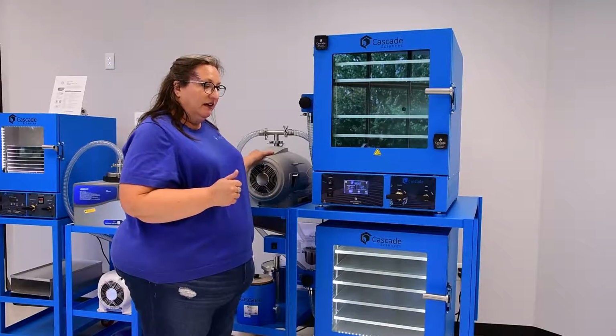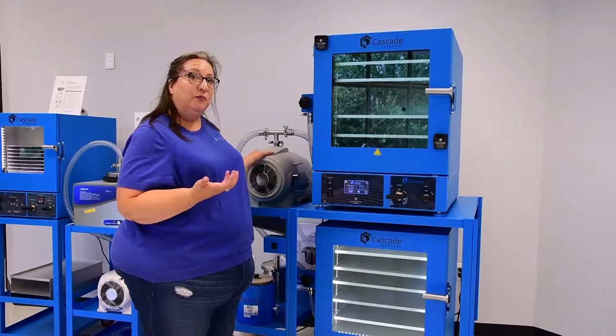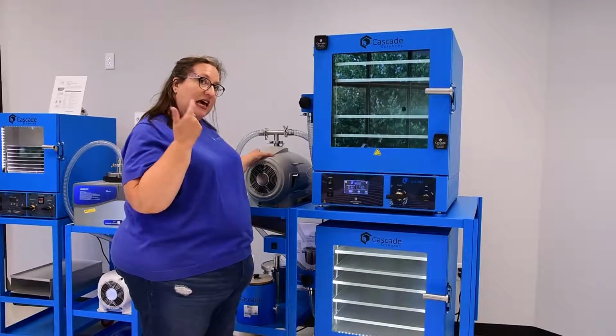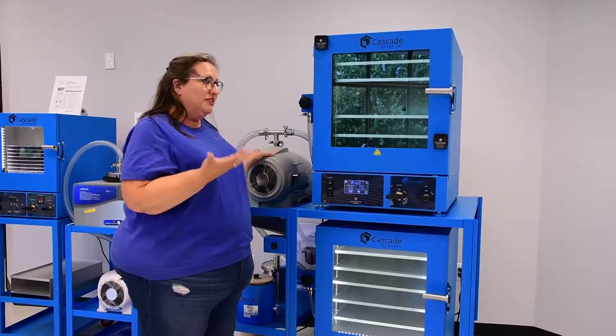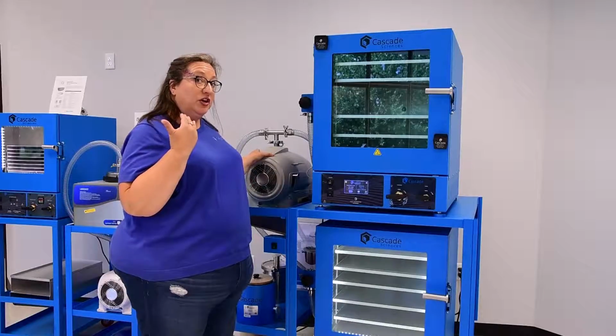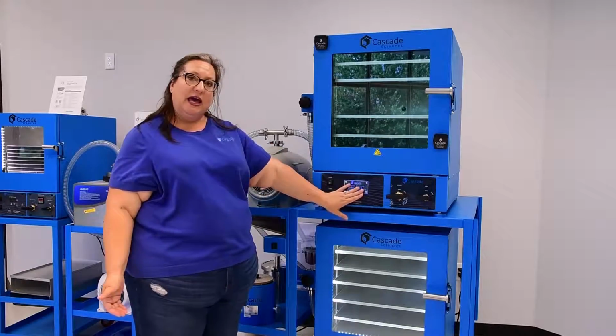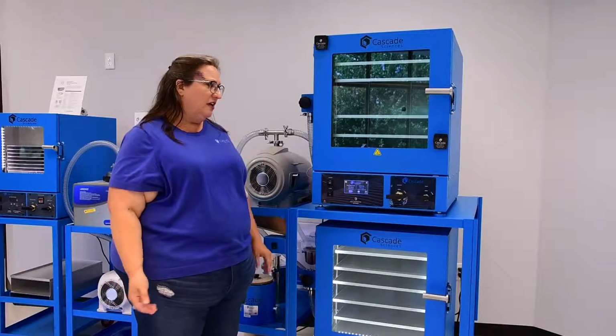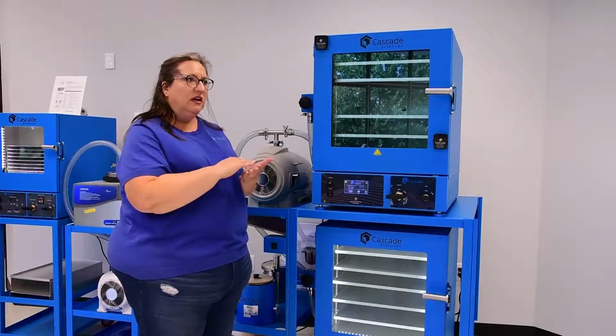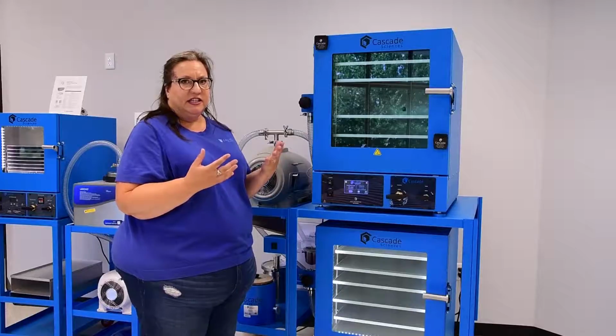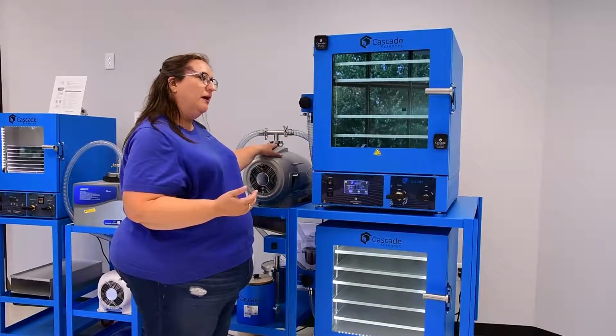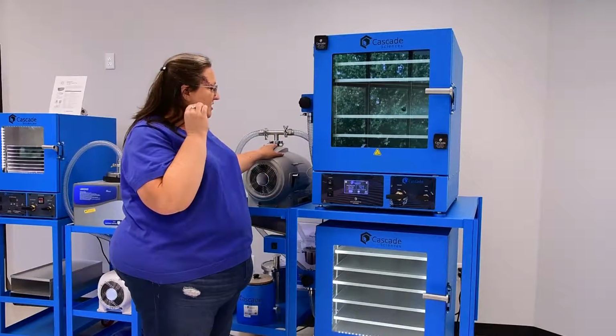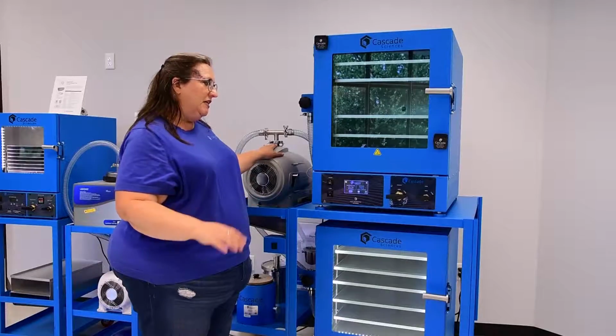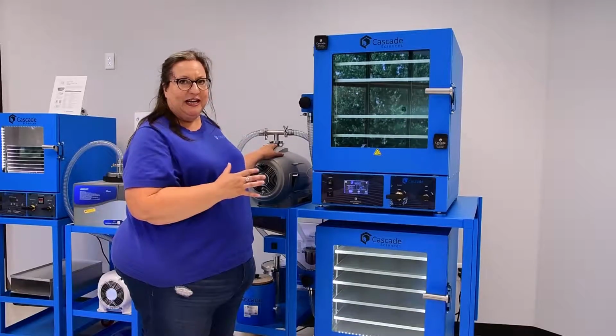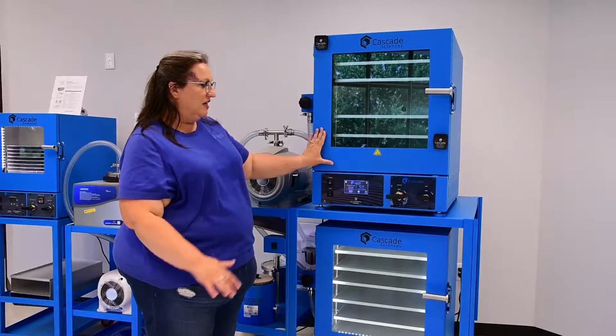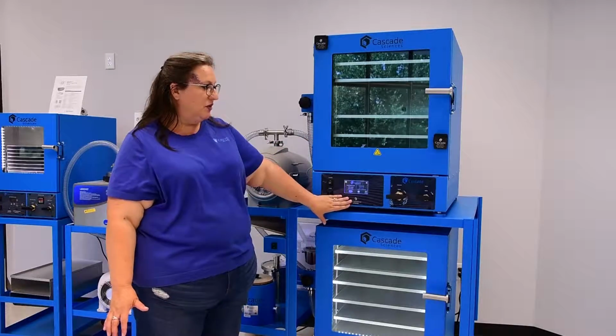It's really good to get to know the sound of your pump. So it's really good to pay attention to how the pump sounds, because when something's wrong with the pump, you're going to know it by hearing it. You're going to know it by how long it takes to get to your vacuum level, and that's actually a really good primary diagnostic tool, is just you knowing that the pump should feel smooth, should sound smooth, and should be easygoing. You can see how already that pump has quieted down and it's evacuated the chamber all the way past 20 inches of mercury.